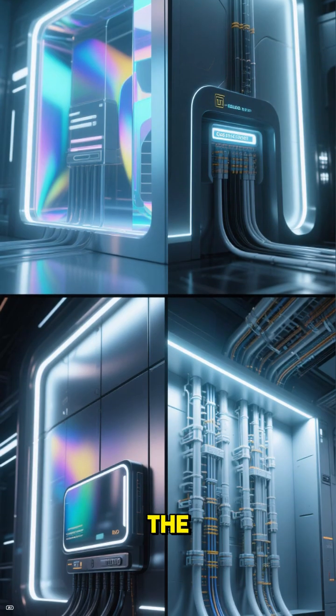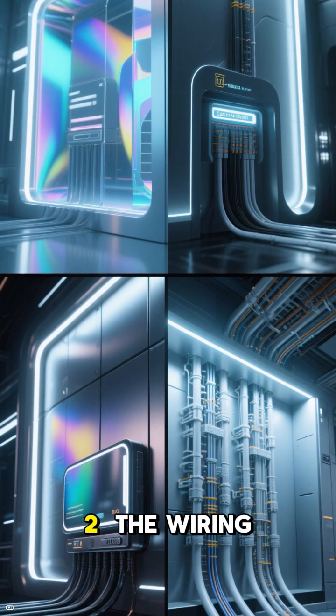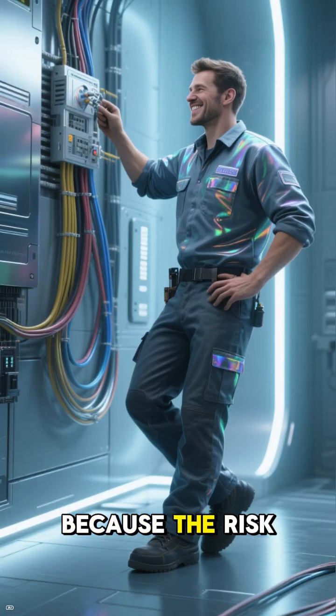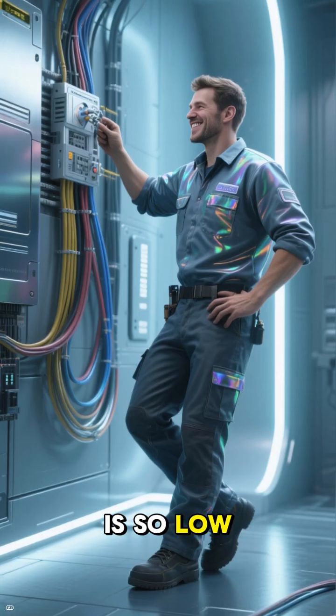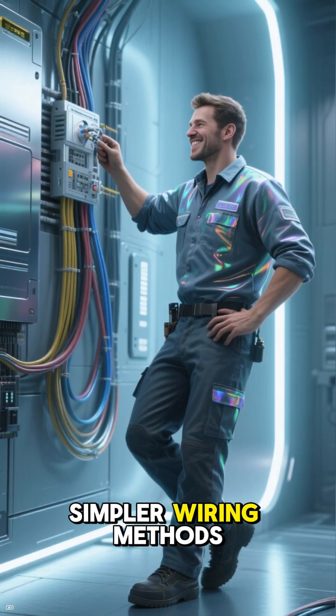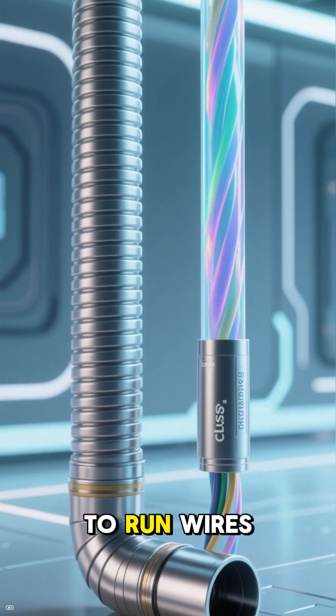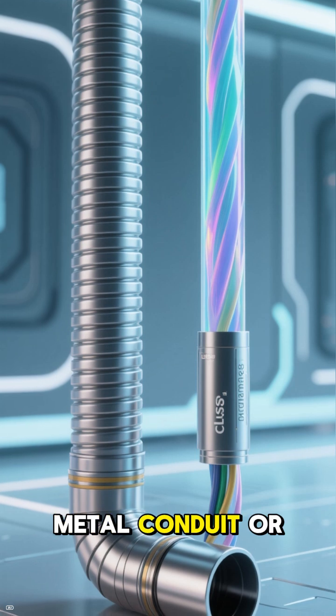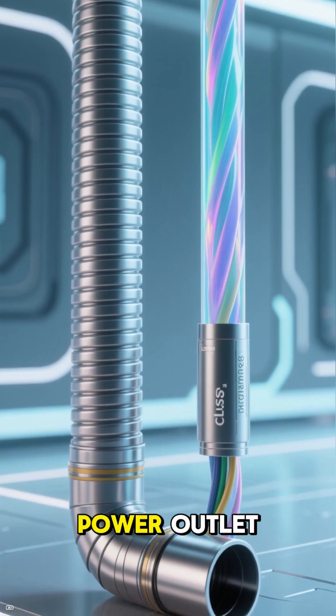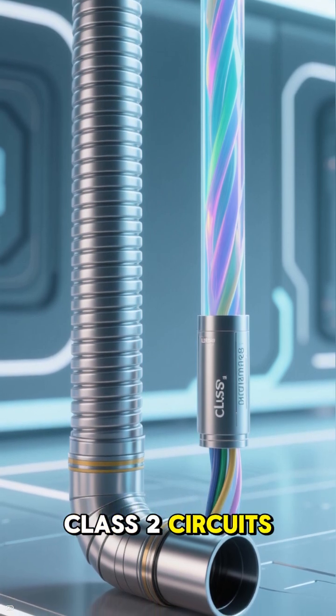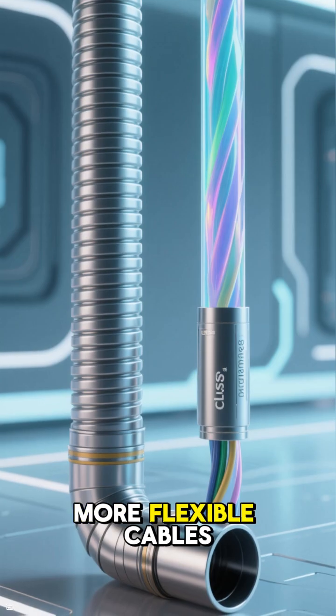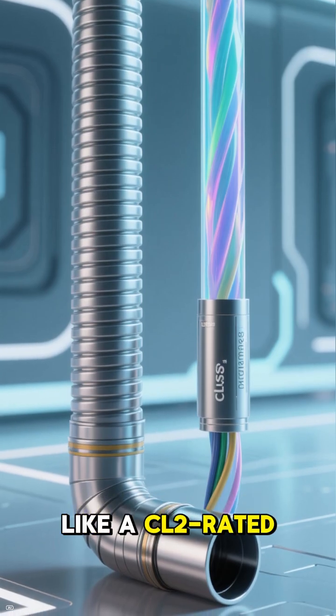This brings us to one of the biggest benefits of Class 2, the wiring advantages. Because the risk of shock and fire is so low, the NEC allows for much simpler wiring methods. Instead of needing to run wires inside rigid metal conduit or armored cable like you would for a standard power outlet, Class 2 circuits can often use less expensive, more flexible cables, like a CL2 rated cable.